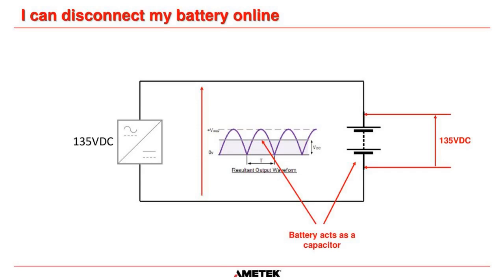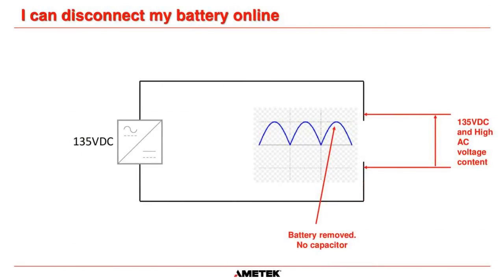So if you remove that battery, okay, what your load circuits are going to see now, instead of a flat DC, they're going to see this high ripple waveform. Okay, it's going from 0 volts up to the peak and then back down again. And some circuits, especially relays, don't like that. Some relays will start to chatter. It's not a good situation. So if you disconnected a battery on an unfiltered charger, you can immediately cause issues on your load circuits. So that is one example of why you can't just go in, open a battery, disconnect, and expect everything to continue to work. That is not the case.